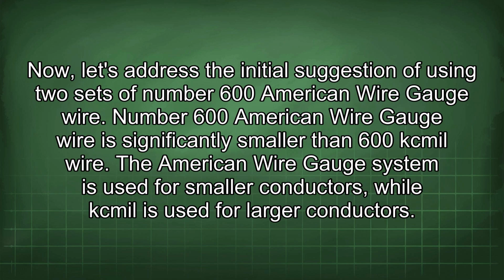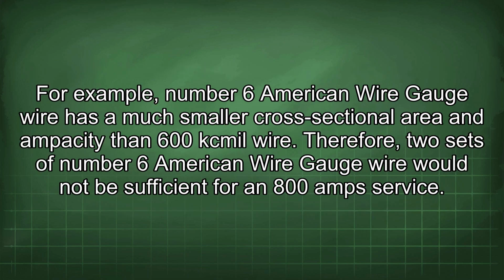Now, let's address the initial suggestion of using two sets of number 600 American wire gauge wire. Number 600 American wire gauge wire is significantly smaller than 600 kcmil wire. The American wire gauge system is used for smaller conductors, while kcmil is used for larger conductors. For example, number 6 American wire gauge wire has a much smaller cross-sectional area and ampacity than 600 kcmil wire. Therefore, two sets of number 6 American wire gauge wire would not be sufficient for an 800 amp service.